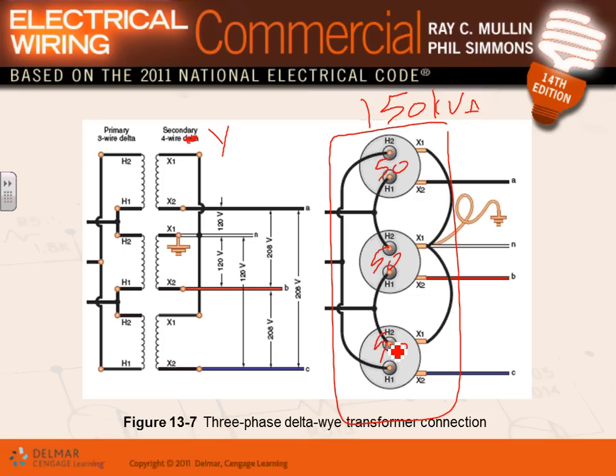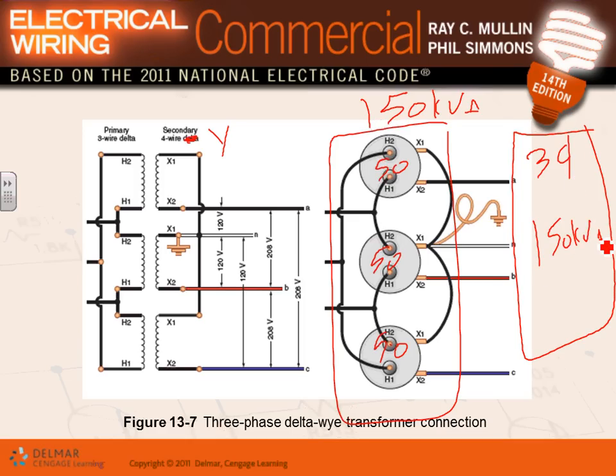until they get another transformer and stick it in there. Cheaper. Now, most bigger commercial buildings don't do it this way, guys. What they do is they have a big fat three-phase transformer equivalent to 150 kVA, sitting in the front or the backyard, feeding your building. Instead of single transformers mounted on a pole, these are one big transformer sitting in the backyard typically.